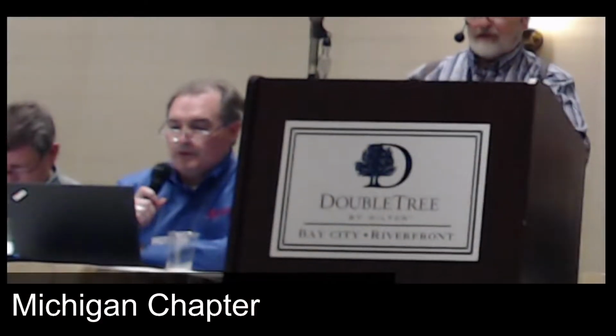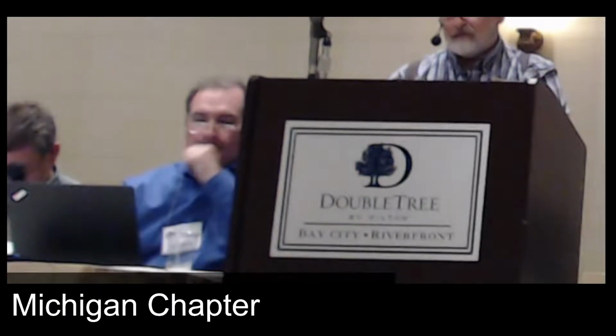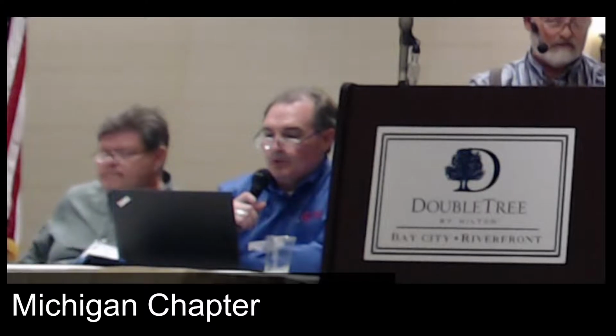Okay, so section 250.32(A), excuse me, requires a grounding electrode system and grounding electrode conductor to be installed at buildings or structures supplied by a feeder or branch circuit. 250.32(B)(1) covers grounding systems and requires an equipment grounding conductor as described in 250.118 to be run with the supply conductors and be connected to the building or structure disconnecting means and to the grounding electrode. The cabinet or cutout box is not listed in 250.118 as a type of equipment grounding conductor. So the grounding electrode conductor should terminate to the equipment grounding bus in the panel where the equipment grounding conductor is terminated. You agree with that? Okay. So no, you can't use the box as a conductor.